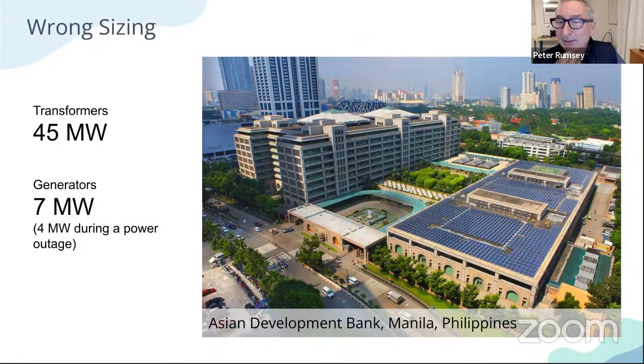But in the Philippines at the time we were looking at this building, they had fairly frequent power outages, like every day or at certain times of the year. So they only had 7 megawatts of generators, and those 7 megawatts would cover the whole load of the building. So the transformers were 6 times bigger than what they needed to be.